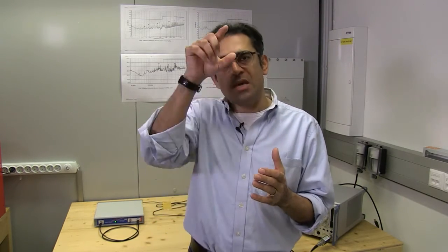Effectively what the standard says is that the current that your product is drawing from the mains has to be as close to a sinusoid as possible. You can take very peaky current to deliver the same amount of power, but of course if the peak of the current that you're drawing is very large, that has got an impact on the cabling and the shielding and so on. So the standard prohibits you from having too much line current harmonics, but that is at much lower frequencies and is effectively around the multiples of the line frequency, which in Europe is 50 Hertz.